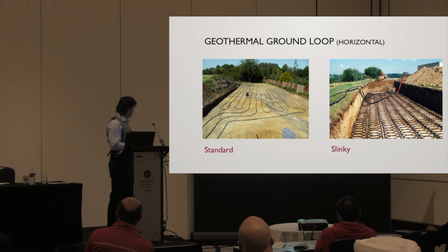Let's put a whole bunch of pipe in the ground, different methods. This is called a slinky. These are usually up to, well, this one looks like an 18-inch pitch, so that'll be about 120 feet long at the most. I actually don't recommend this. These are side by side by side. That's one massive energy you're trying to take out of the ground there. But at least it's deep. Look at the depth they got here.